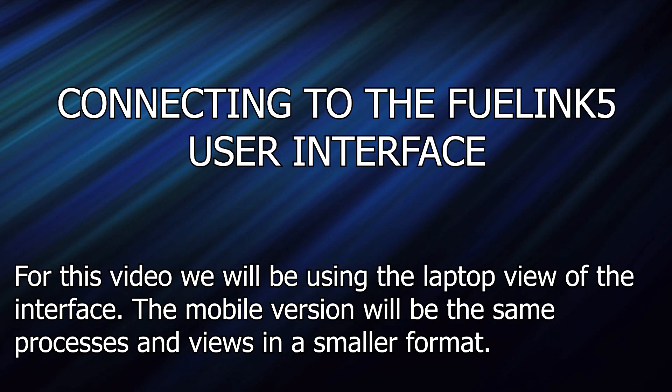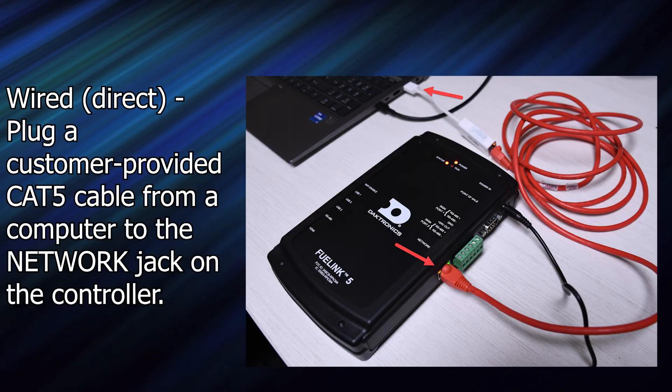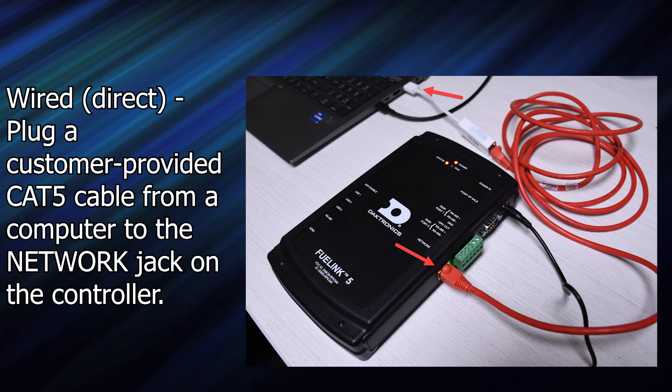Let's kick off by showing you the different options for connecting to the user interface. The first option would be the wired network. To connect this way, you will plug a customer-provided Cat5 cable into the network jack on the controller. The other option is wired direct, where you would plug a customer-provided Cat5 cable from a computer to the network jack on the controller.